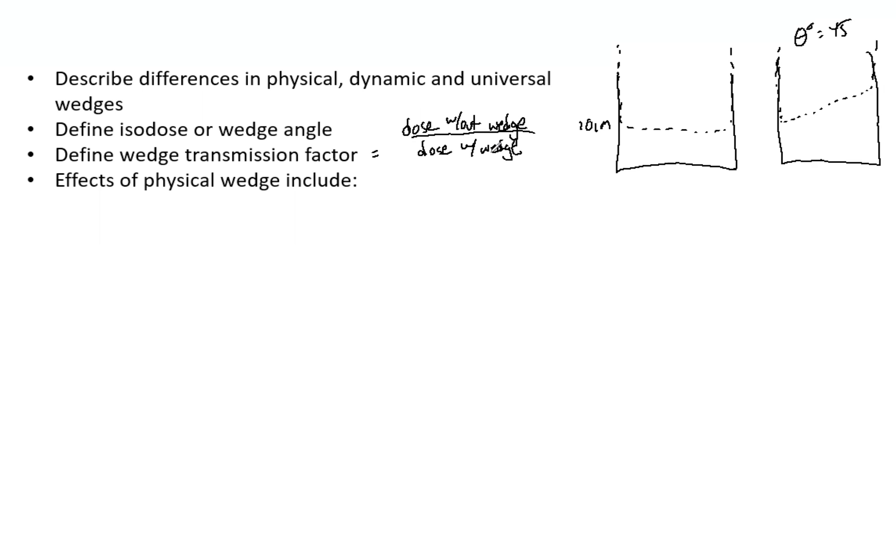You want to put the chamber past D-max, something like at 10 cm. These factors are typically less than one because there's an attenuation. You're going to have less dose with the wedge compared to without.